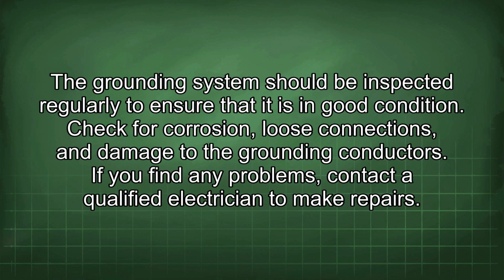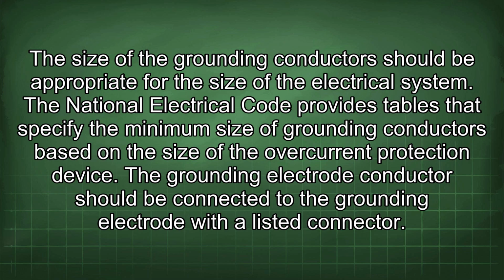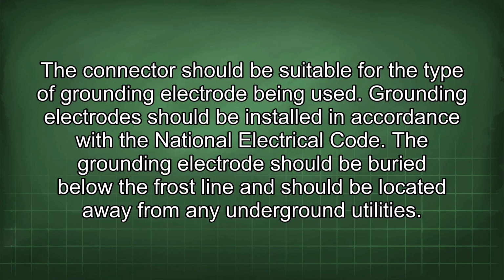The grounding system should be inspected regularly to ensure that it is in good condition. Check for corrosion, loose connections, and damage to the grounding conductors. If you find any problems, contact a qualified electrician to make repairs. The size of the grounding conductor should be appropriate for the size of the electrical system. The National Electrical Code provides tables that specify the minimum size of grounding conductors based on the size of the overcurrent protection device. The grounding electrode conductor should be connected to the grounding electrode with a listed connector. The connector should be suitable for the type of grounding electrode being used.